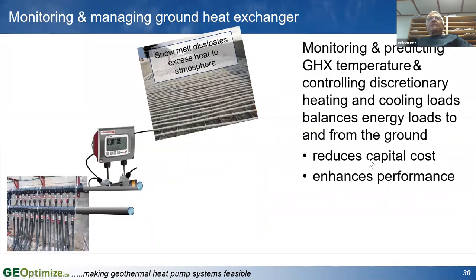So when we're looking at things like monitoring the system, you can actually manage how much energy you're putting into the ground. For example, you can divert some of the heat away from the ground loop and dissipate it into a snowmelt system. That was done in an IKEA store in Denver a number of years ago, where they've got 35,000 square feet of area in the loading docks. All that's there for is to dissipate excess heat, divert it away from the ground heat exchanger and make some beneficial use of it. It happens to melt snow when it does snow in Denver, but most of the time we can dump heat whether there's snow there or not. So it's what I would term a discretionary heating load. We can divert heat away from the ground loop, avoid putting it into the ground, avoid having to build more ground loop, and make some beneficial use of that heat at the same time.